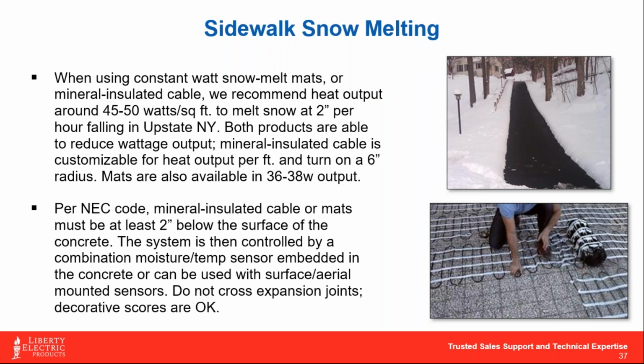And we can get down around even 40 watts a square foot just to pick up a little energy savings, but you're going to be a little bit more down towards that inch to inch and a half per hour as far as the melt rate goes. And then, of course, the most energy efficient, if you can believe it, is to just maintain a slab temperature throughout the entire winter itself. So if you literally just put your sidewalk on at 33 or 34 degrees from November until April, you won't be able to melt down a foot very quickly, that's for sure. It's going to take some time for that system to catch up and melt down a more sizable snowfall, but it actually uses considerably less, like up to 65% less energy to just maintain a slab temperature throughout the entire winter versus doing it on demand.